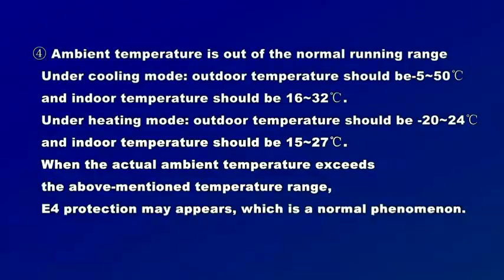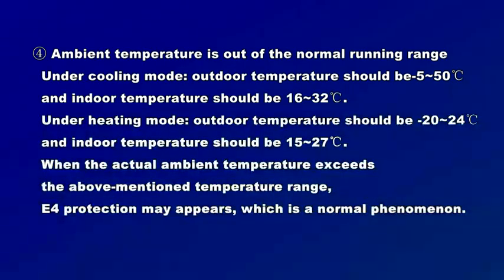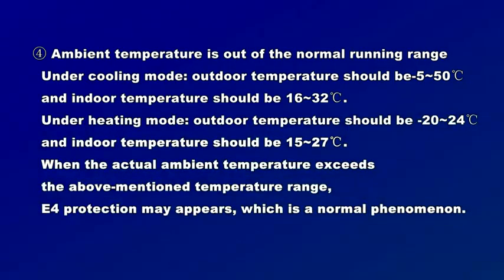4. Ambient Temperature is out of the normal running range. Under cooling mode, outdoor temperature should be -5 to 50°C, and indoor temperature should be 16 to 32°C. Under heating mode, outdoor temperature should be -20 to 24°C, and indoor temperature should be 15 to 27°C. When the ambient temperature exceeds the above-mentioned range, E4 protection may appear, which is a normal phenomenon.